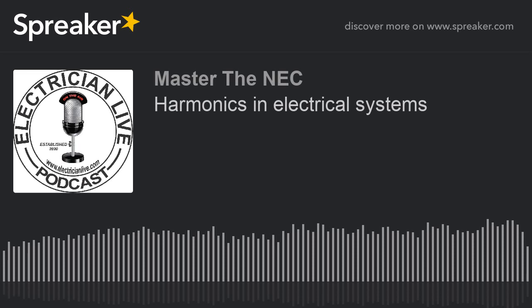Another way that engineers do this, and I don't like this way because I pay for something, I want to get something out of it. A lot of times the side effect of the harmonics is it's terrible for transformers. So some engineers will actually derate or reduce the amount of load that a transformer can handle. That's going to result in having multiple transformers because of the elevated harmonics that cause the overheating, and because of that, that extra current generated by the inefficiency of the harmonic distortion, they will break it out.